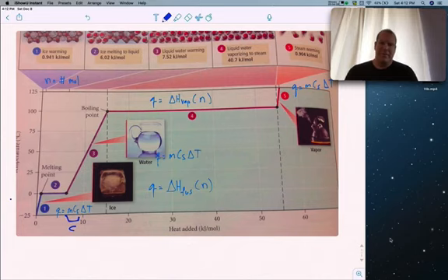So almost every place, and Navy vessels also superheat the steam, and that's nice because when you have a turbine, the steam comes in, steam comes out, and then the steam just loses energy. So the energy loss equals the energy transfer to the turbine. In saturated steam, the steam will condense on the turbine, which will make it less efficient, and also tends to damage and corrode the turbine at a more quick rate.